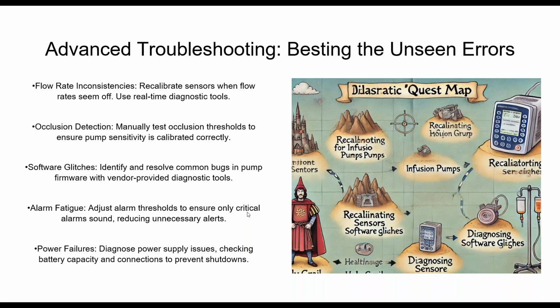So flow rate inconsistencies, number one thing to check is first of all, check that the flow rate inconsistencies being reported actually exist, and then recalibrate. I will tell you that you don't want to go ahead and recalibrate without understanding what the actual problem was for a variety of reasons, but the main reason is it's a waste of time. I can't say this enough: don't waste your time calibrating something you don't know was actually off to begin with, unless it's part of your maintenance plan, where you know it typically drifts. But when I say flow rate inconsistencies, I mean those things reported to you or that you observe during routine maintenance or an investigation.